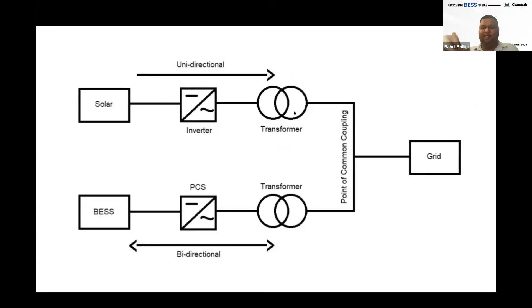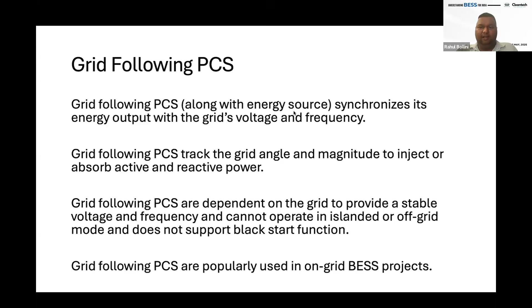Typically, most projects back in the day would follow grid-following PCS. Grid-following works well, but if there's a blackout or power outage, it cannot do anything. It does not have an islanding function. Islanding function is having its own way of operating rather than depending on the grid. Typically this depends on the grid to maintain voltage and frequency. Grid-following is not something which can support during a blackout, and that's why it's not used for off-grid projects.